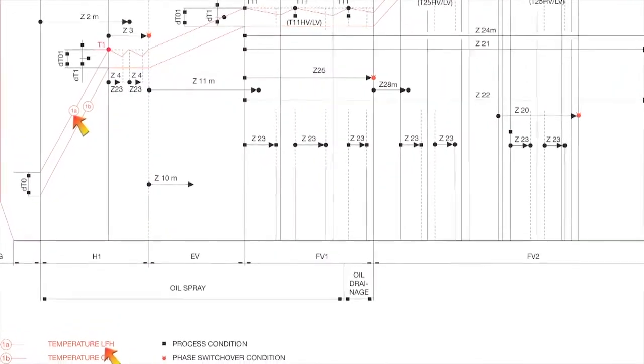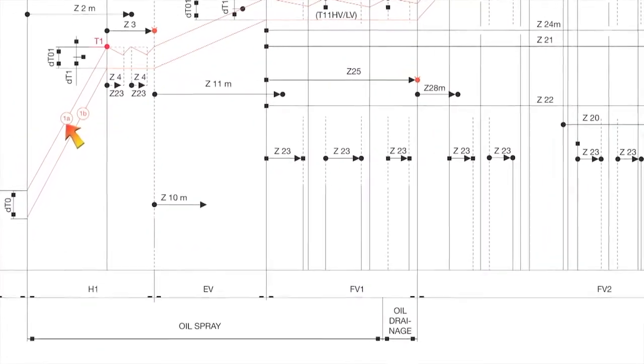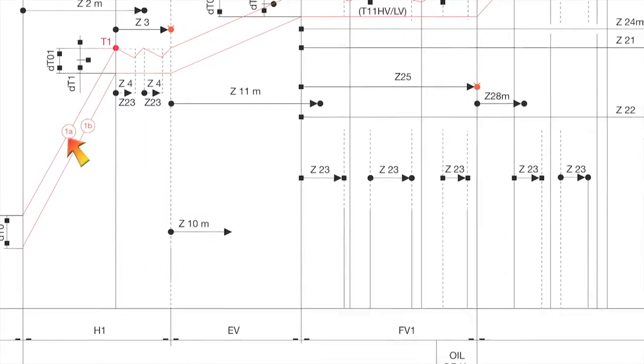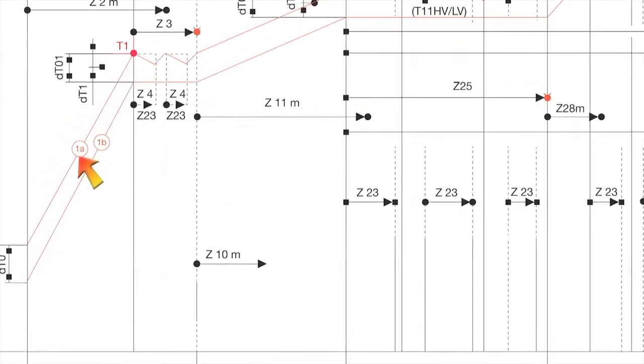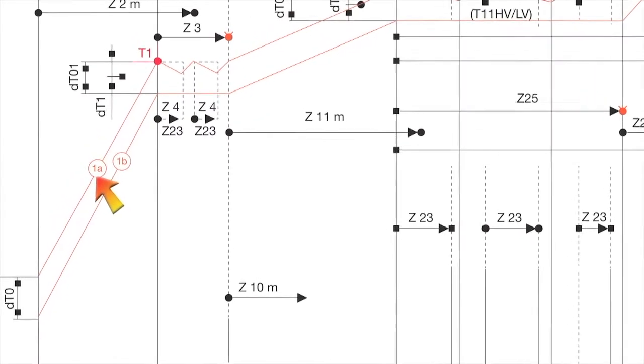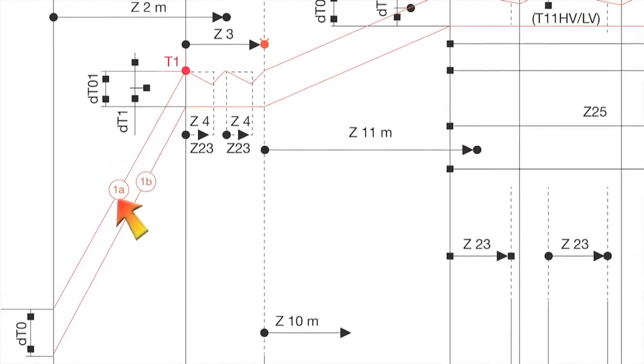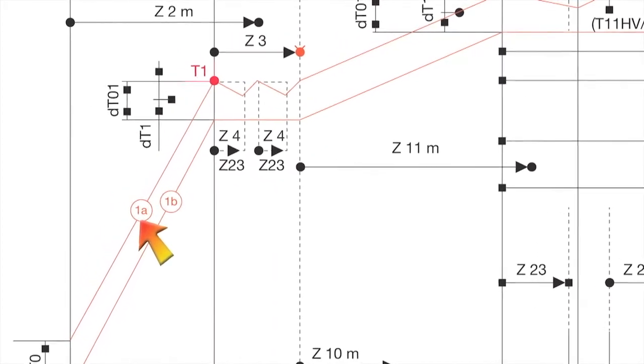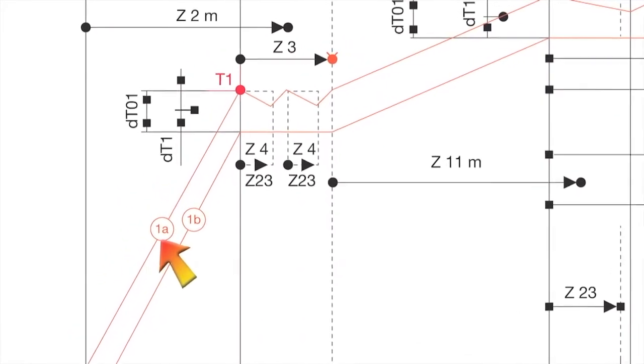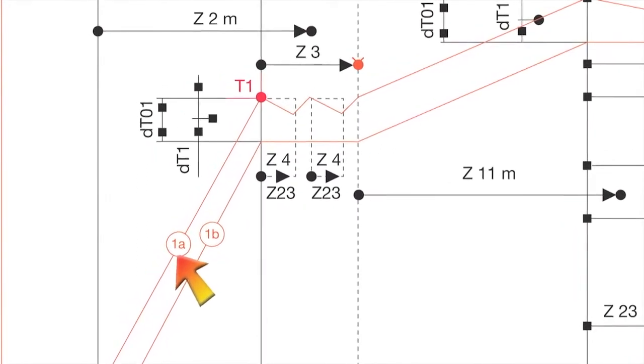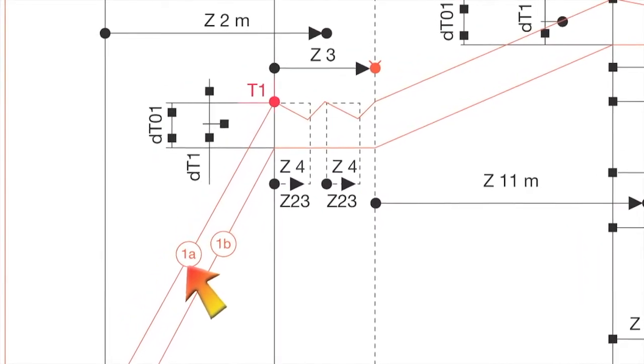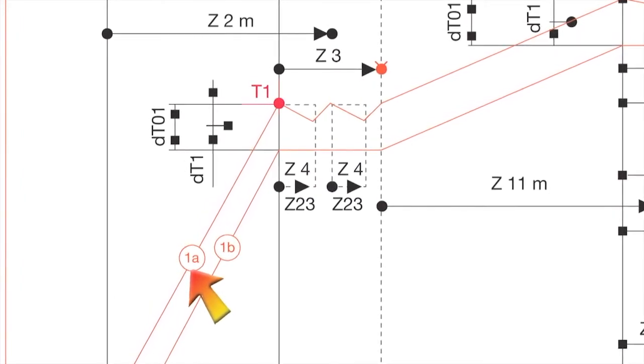Overview. Heating 1. The transformer is heated by means of LF current in combination with oil circulation or hot oil spray to the first temperature set point. Once reached, the set point of the converter will stabilize the temperature inside the transformer by stopping and starting the current injection. If a combination with oil spray is selected, vacuum will be applied at the same time. The first temperature step is kept constant for a certain time, Z3, so that a uniform temperature distribution in the insulation can take place.